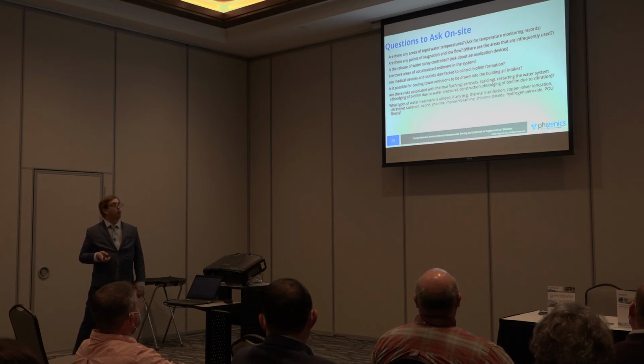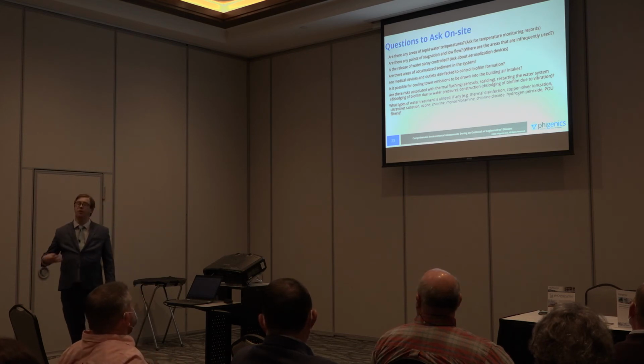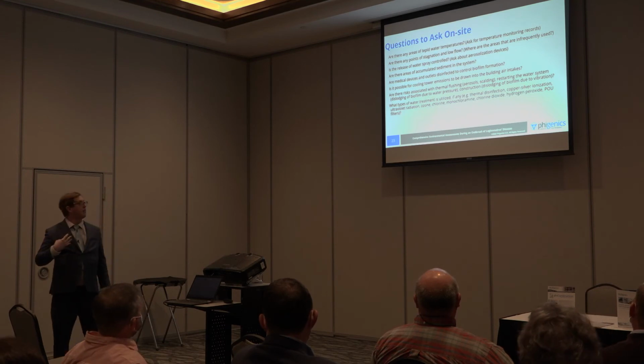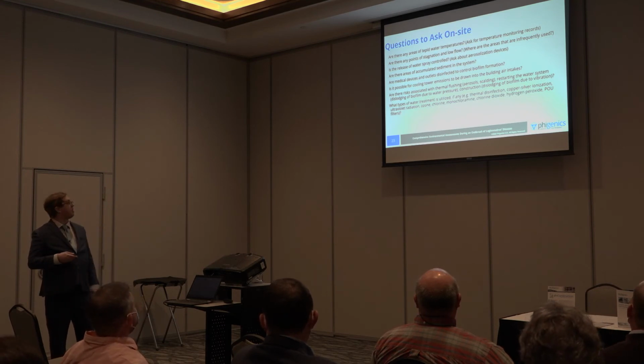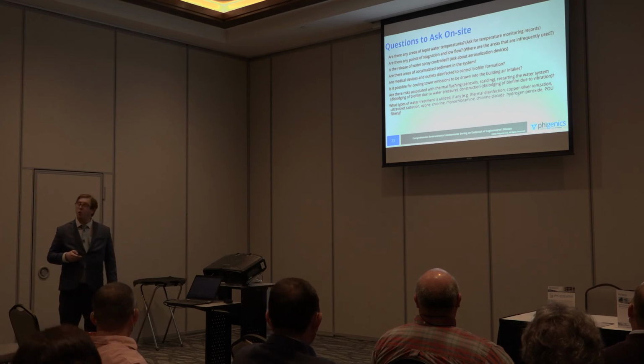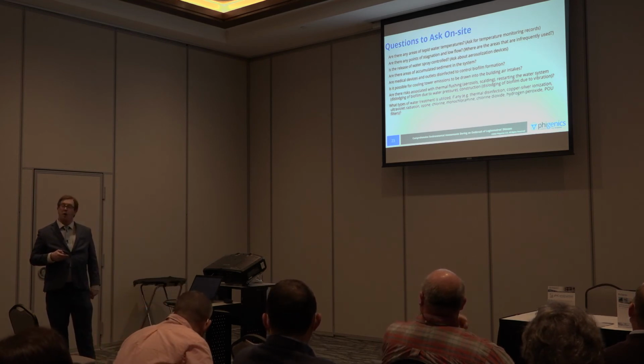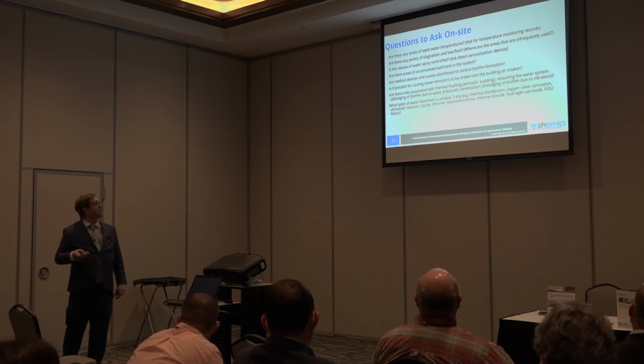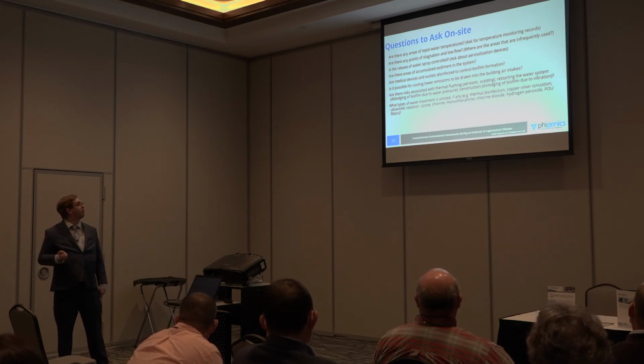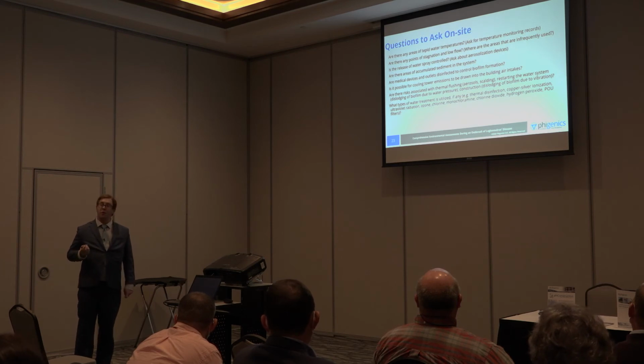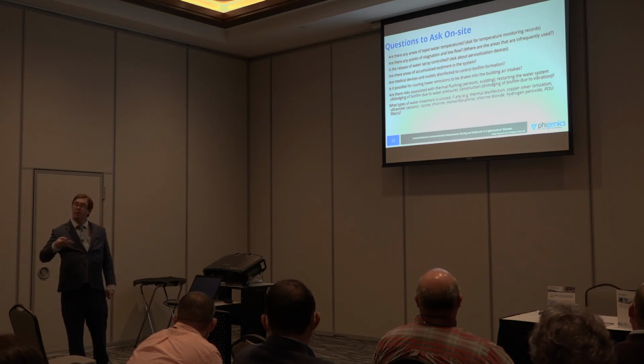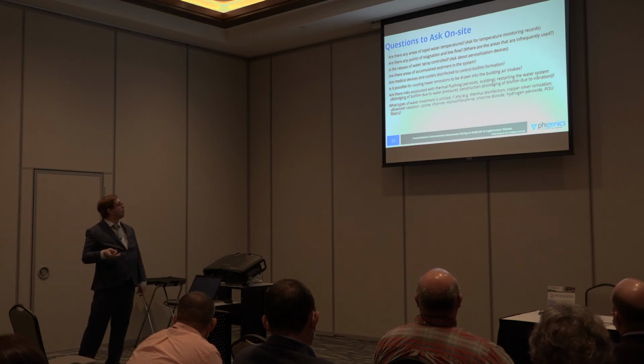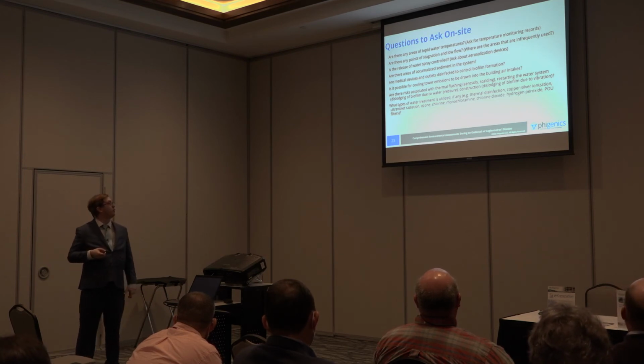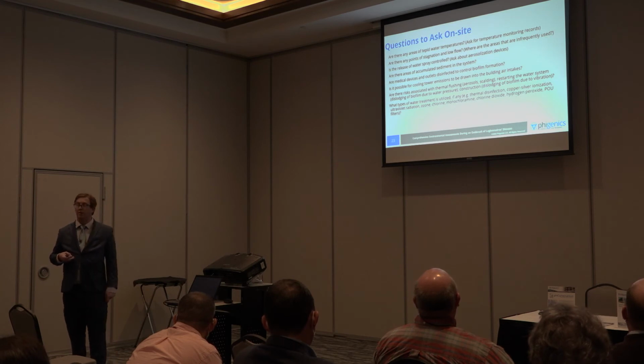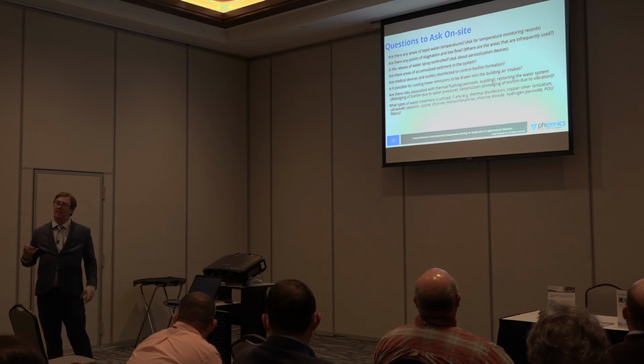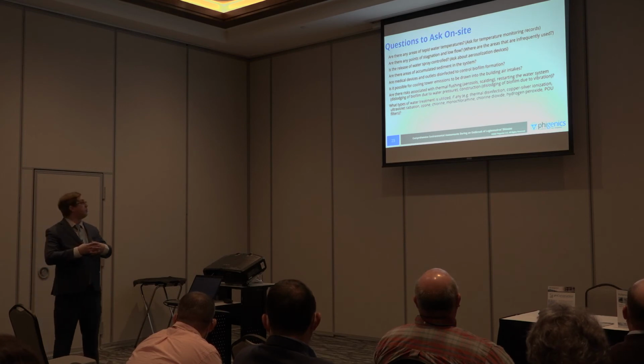Is the release of water spray controlled? Remember, aerosolization causes people to acquire droplets contaminated with Legionella. Are there areas of accumulated sediment in the system? Are medical devices, if they have any, and outlets disinfected to control biofilm formation? Is it possible for cooling tower emissions to be drawn into building air intakes? Are there risks associated with thermal flushing, restarting the water system, or construction? So is there a potential for dislodging biofilm that's collected in the internal components of your building system?